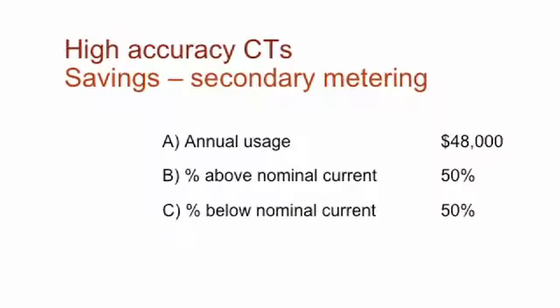So if we took the annual usage times the percentage of time above nominal current, and you multiply that out times 0.0015. Now where does the 0.0015 come from? Well, that's the difference between 0.3 and 0.15% accuracy. So that'd be the differential between those two. So if you multiply that out at times of above nominal current, you can save $36 a year. If we take a look at annual usage times the period of time below nominal current times 0.0045. Again, that's the difference between 0.6% and 0.15%. Okay? You could save $108.